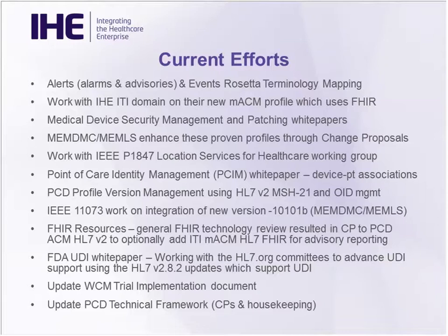PCD is a domain within IHE, but there are other domains within IHE as well, and we do pay attention to what they do that might interact or run parallel to what the PCD domain does. The IT Infrastructure, or ITI, domain within IHE implemented a mobile ACM profile, which makes use of the FHIR HL7 protocol instead of HL7 version 2. We do pay attention to that, and we've actually made an improvement to our ACM profile to allow FHIR-based messaging for the reporting of alerts.